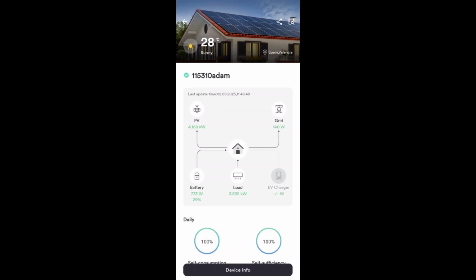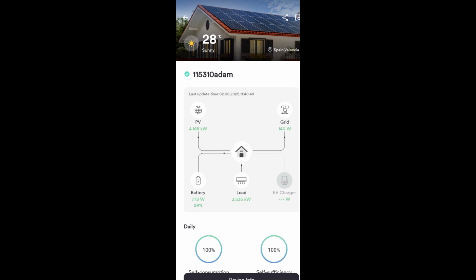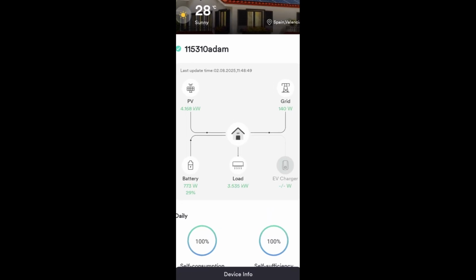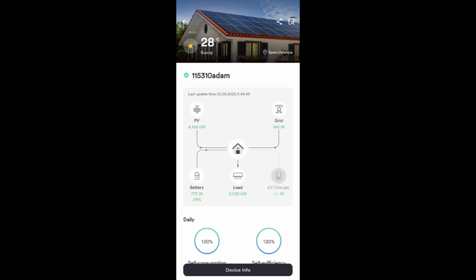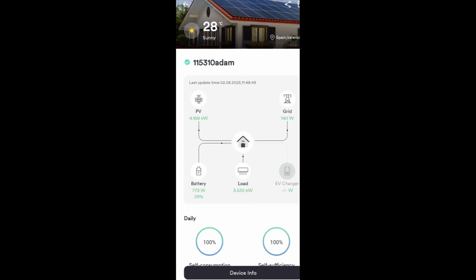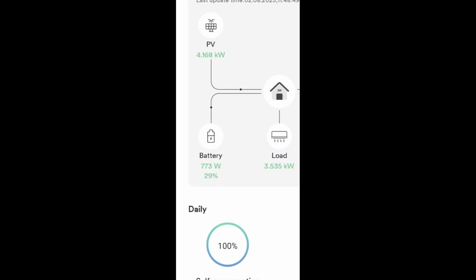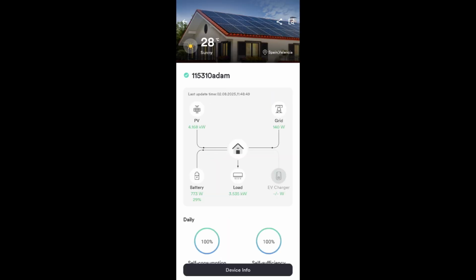So this is the app that came along with the inverter and gives you an overview of the whole system. On the top left you can see the PV, that's the solar panels, currently producing just over 4 kilowatts. The load on the house there in the middle, 3.5 kilowatts, and the battery's charging. It's at 29% at the minute, charging at 773 watts. With the grid, we're taking 140 watts from the grid because the inverter needs a little bit of power to run.